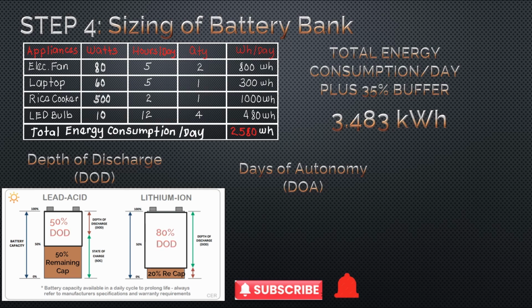For example, I will apply 2 days autonomy. This means that when you use 1 day autonomy, you will need only 5 batteries of 100 Ah each. So for 2 days autonomy, you need another 5 batteries of 100 ampere hour each. So the total battery needed is 10 batteries of 100 ampere hour each.